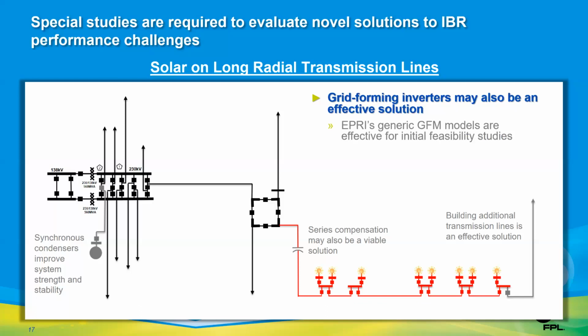An emerging solution, which is one of my favorites at this point, although it still needs to be vetted more, is grid forming inverters. We performed initial analysis with EPRI's generic GFM inverter models in both PSS/E and PSCAD, and we found that it eliminated our performance issues. And we expect that this will be way more cost effective than all of our other options. We still have some work to do here.